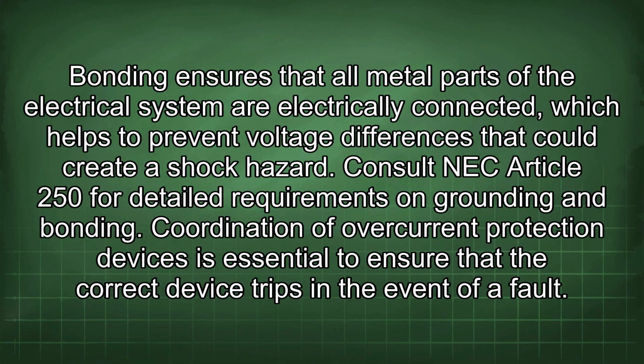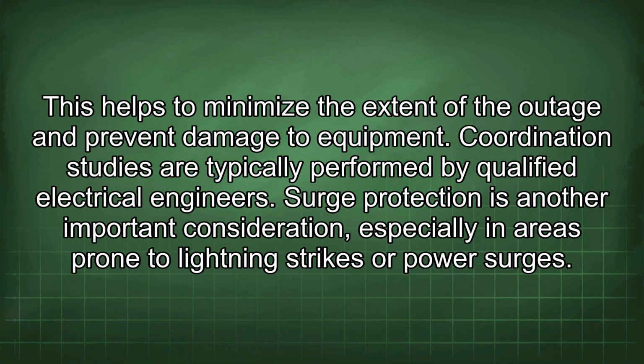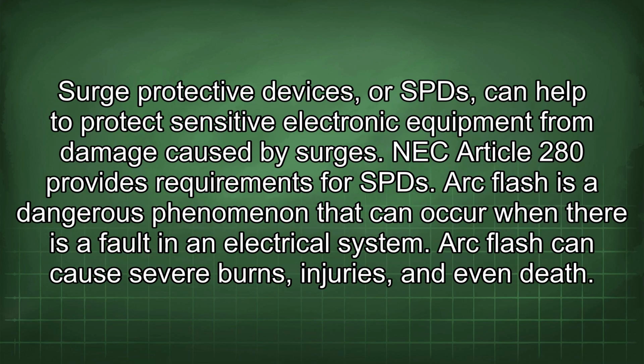Coordination of overcurrent protection devices is essential to ensure that the correct device trips in the event of a fault. This helps to minimize the extent of the outage and prevent damage to equipment. Coordination studies are typically performed by qualified electrical engineers. Surge protection is another important consideration, especially in areas prone to lightning strikes or power surges. Surge protective devices, or SPDs, can help to protect sensitive electronic equipment from damage caused by surges. NEC Article 280 provides requirements for SPDs.